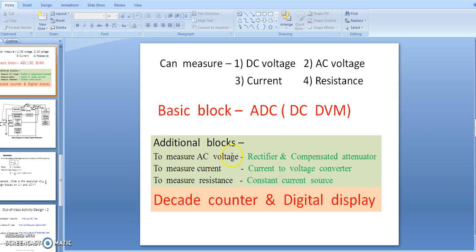To measure AC voltage, an additional block is required: a rectifier and a compensated attenuator. For DC voltage measurement, a normal attenuator — just a voltage divider — is sufficient. But for AC voltage, we require a compensated attenuator so that the attenuation factor is independent of frequency. That is why an R and C parallel combination (RC) is used — that is the compensated attenuator.